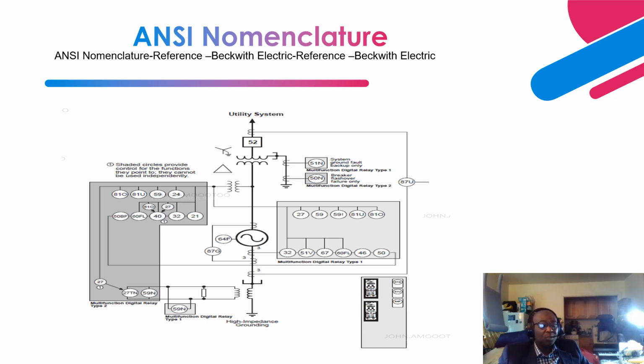And what is an over frequency condition? Let's say the generator has a nominal operating frequency, like 60 hertz, right? The manufacturer will allow you to go beyond that, let's say 60.5 hertz or 61 hertz.